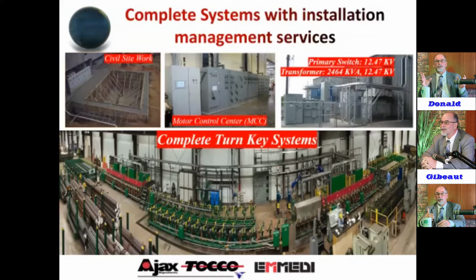At Ajax Tocco Magnethermic, and through our Amity group, we can offer install services, which includes all the civil work. To the upper left, you see a quench pit for heat treat quench and temper lines. This particular one is very large, but it's for 36 tons an hour, so quite a volume of quench water goes in there. We do all of the motor control centers, the input transformers, switch gear. You know, we're typically working with a 12.47 kV line.